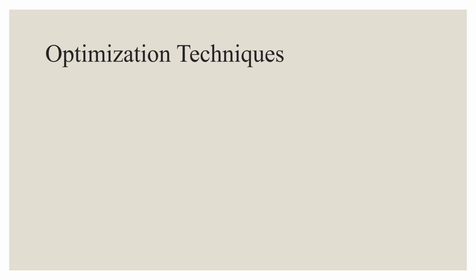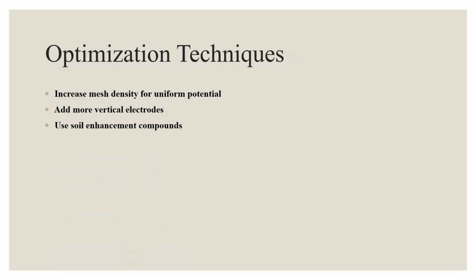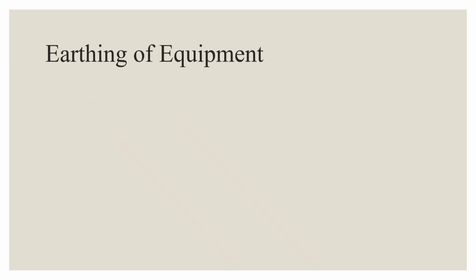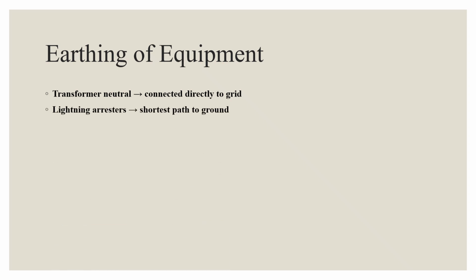So to optimize the performance, we can increase mesh density for better potential uniformity, and more electrodes, or use soil enhancement compounds to lower the resistivity. Adding a crushed rock surface layer also helps by providing high surface resistivity and reducing the step voltage. All the metallic equipment must be properly earthed, means the transformer neutrals are connected directly to the grid. Lightning arresters have the shortest possible path to ground, and control panels are grounded via copper strip. Proper earthing ensures both functional and protective grounding in substations.